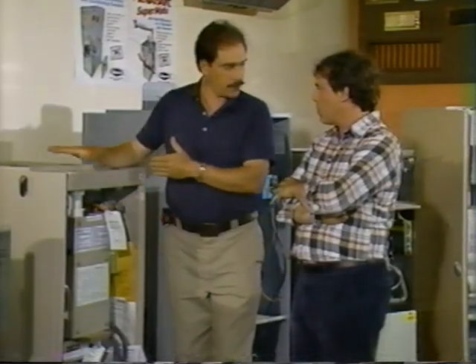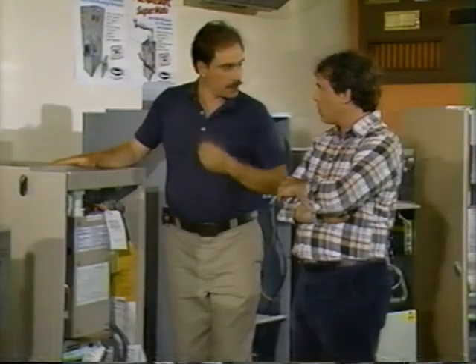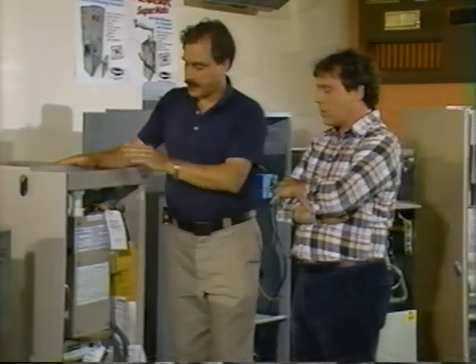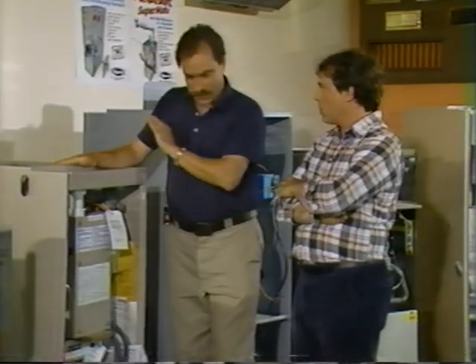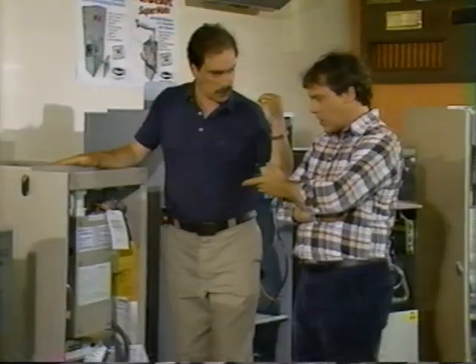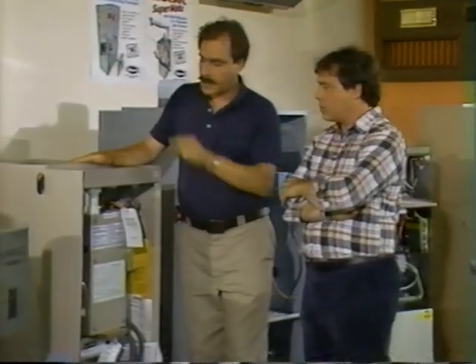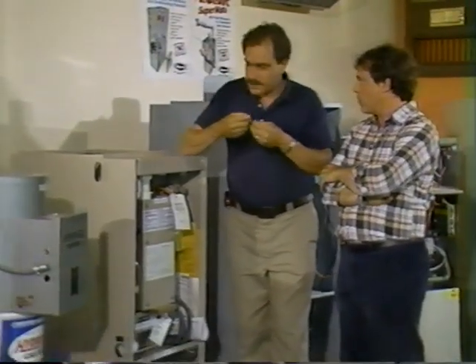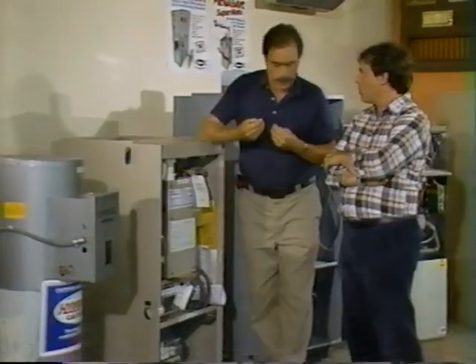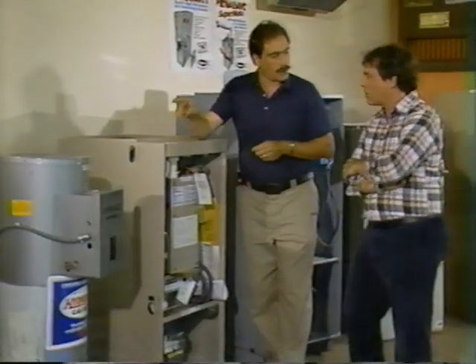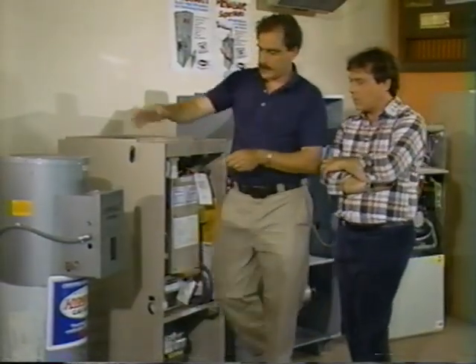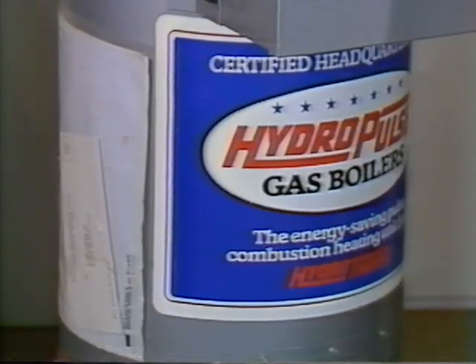Now all of the units that we've been looking at up to this point have been forced air furnaces. It's also possible to use this technology, which is somewhat different than the conventional technology we've been looking at. Pulse. What it's doing is actually it's a bit more like an internal combustion engine. You can use the same technology in forced hot water, or hydronic, and in this case we have a boiler that does exactly the same thing.